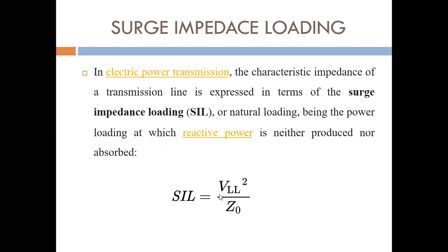Increasing the surge impedance loading is the common method for increasing the power limits of heavily loaded long transmission lines. But there is a limit beyond which it is neither economical nor practicable to increase the value of VR. While increasing the value of VR, we run into some limits.